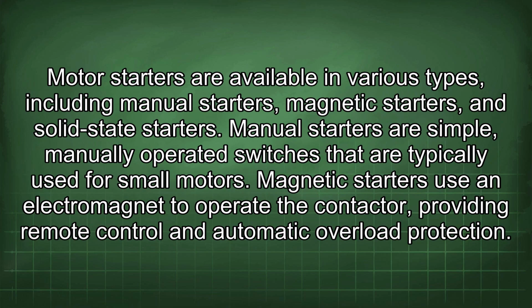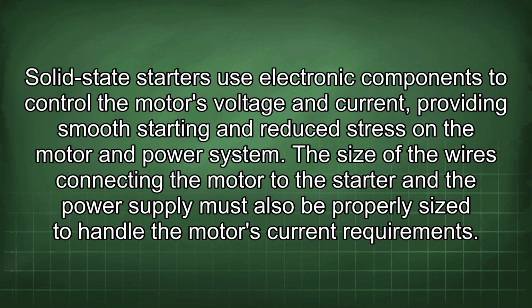Motor starters are available in various types, including manual starters, magnetic starters, and solid-state starters. Manual starters are simple, manually operated switches that are typically used for small motors. Magnetic starters use an electromagnet to operate the contactor, providing remote control and automatic overload protection. Solid-state starters use electronic components to control the motor's voltage and current, providing smooth starting and reduced stress on the motor and power system.